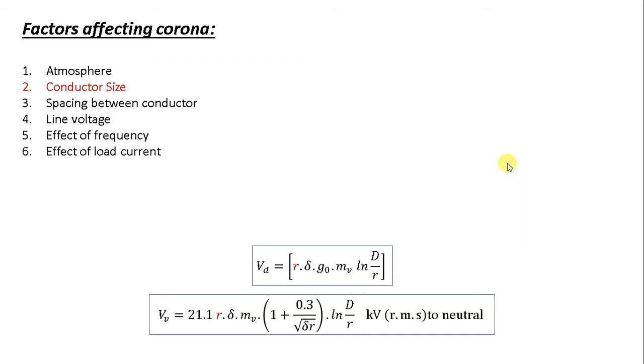The second factor is conductor size. The corona effect depends upon the shape and condition of the conductor. Here, r is the radius of the conductor, and we have factors m0 and mv. A rough and irregular surface gives rise to more corona because unevenness of the surface decreases the value of breakdown voltage, Vd and Vv.